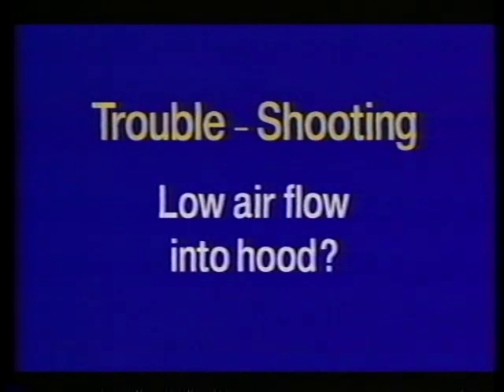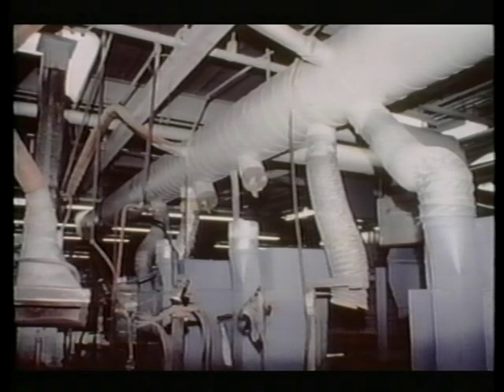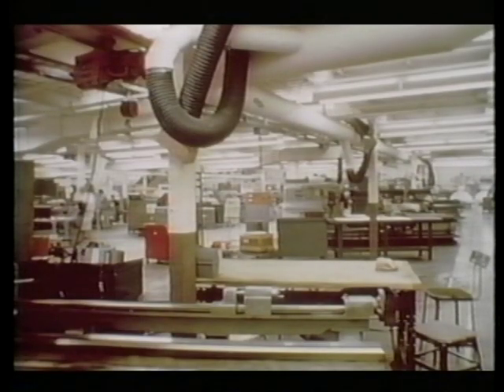Let's talk about troubleshooting existing systems. A major complaint is a lack of sufficient airflow into the hood. Look for plugged, dented, crimped, or damaged ducts; slipping fan belts; the fan turning in the wrong direction; worn-out fan blades; misadjusted gates and dampers; or a clogged air cleaner. When constant plugging of ducts is the problem, check the transport velocity — is it adequate to prevent settling? If employees complain about the hood or refuse to use it, check whether the hood interferes with work or simply doesn't provide good emission control.